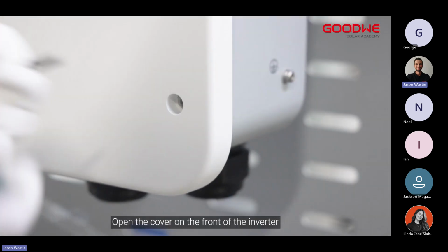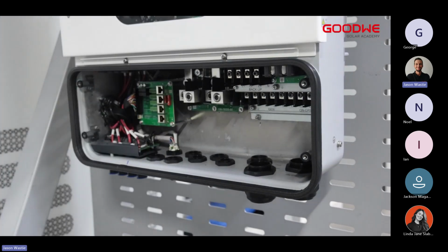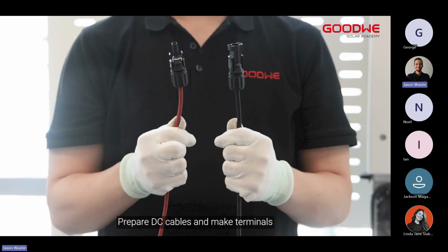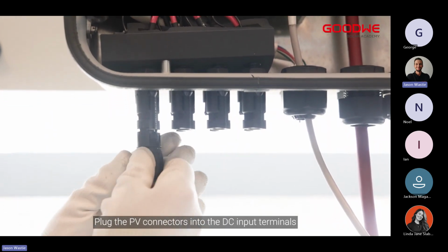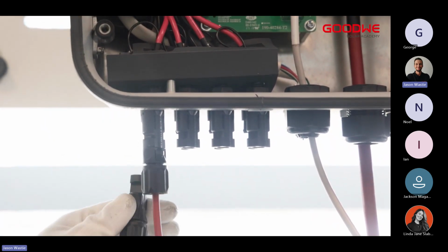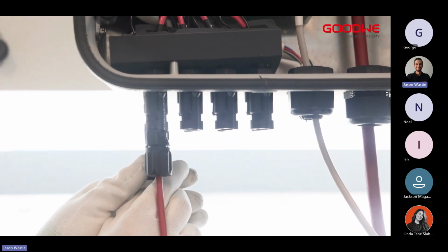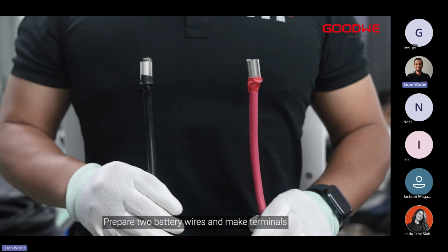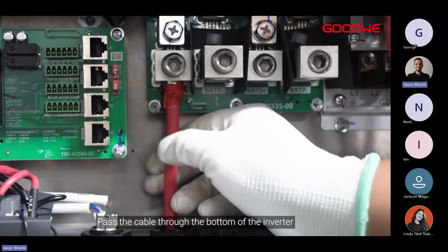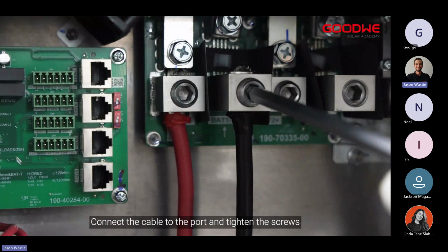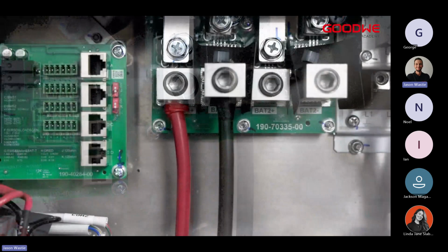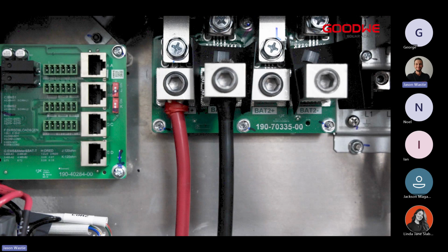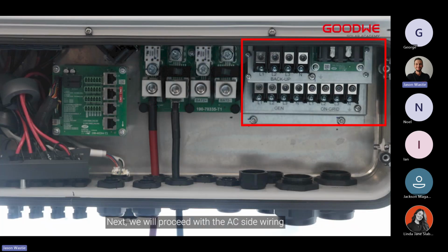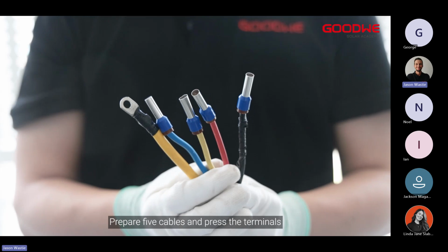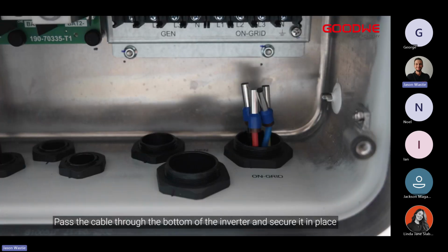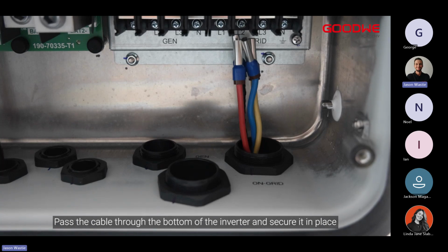Open the cover on the front of the inverter. Prepare DC cables and make terminals. Plug the PV connectors into the DC input terminals. Prepare 2 battery wires and make terminals. Pass the cable through the bottom of the inverter. Connect the cable to the port and tighten the screws. Next, we will proceed with the AC side wiring. Prepare 5 cables and press the terminals. Pass the cable through the bottom of the inverter and secure it in place.